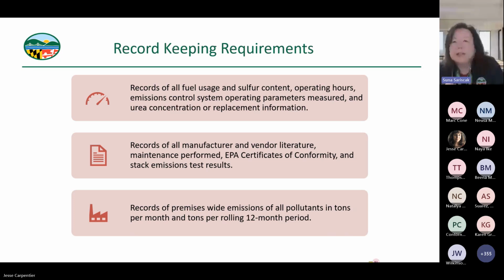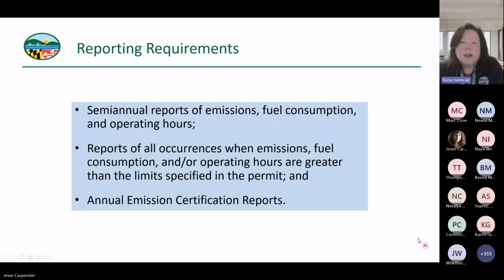Basically, we're going to have them report that information to us semi-annually. Also, if a rolling 12-month period goes over 25 tons, they have to report that within 15 days, so we can check back on any occurrences where emissions, fuel consumption, or operating hours are greater than the limit specified in the permit. They also have to submit annual emission certification reports.